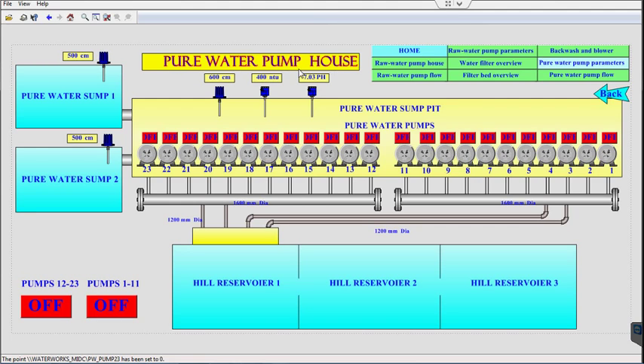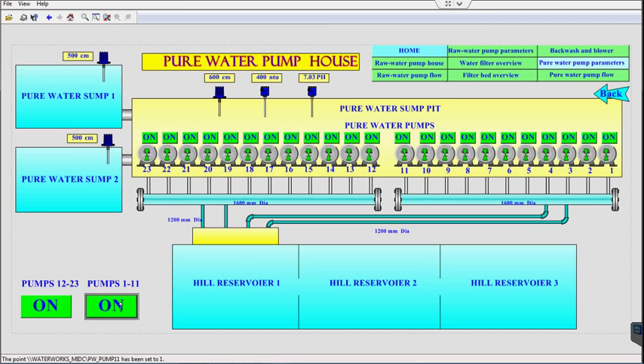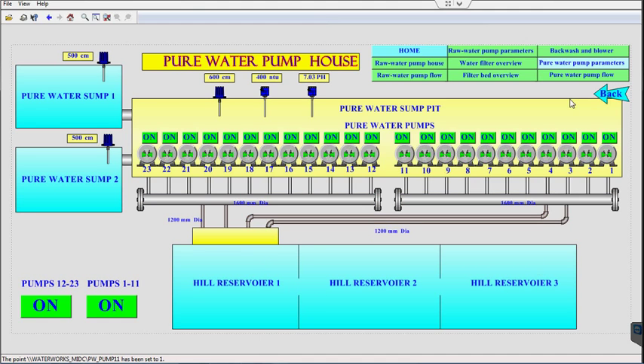Pure water pump house. Filtered water from the filter is collected at the pure water sump, which is provided with ultrasonic level transmitters. Water from the sump is passed to the pure water pit. Twenty-three pure water pumps are located on the pure water pit: 17 are of 750 HP and the remaining 6 are of 600 HP. The pure water sump is provided with turbidity, pH, and chlorine transmitters, and the data received from these transmitters is recorded in SCADA. Each pure water pump can be started and stopped from the central control room, and water delivered from the pure water pump is stored in the hill reservoir.